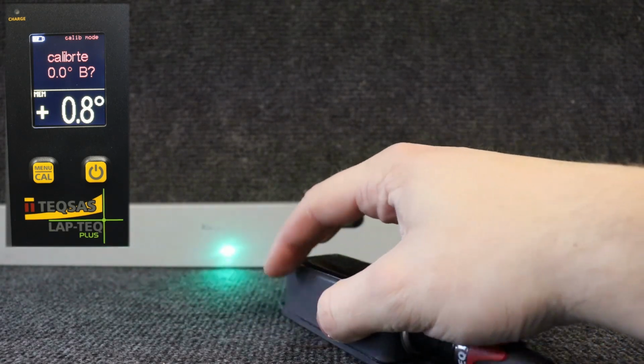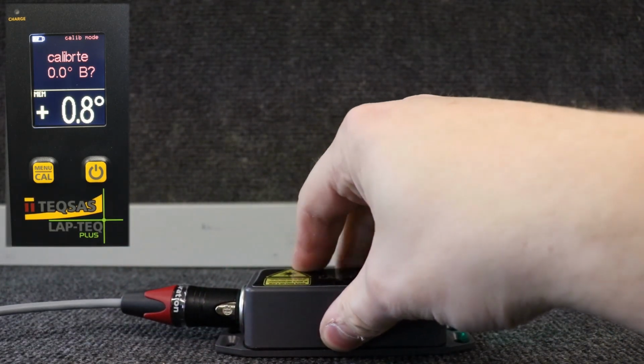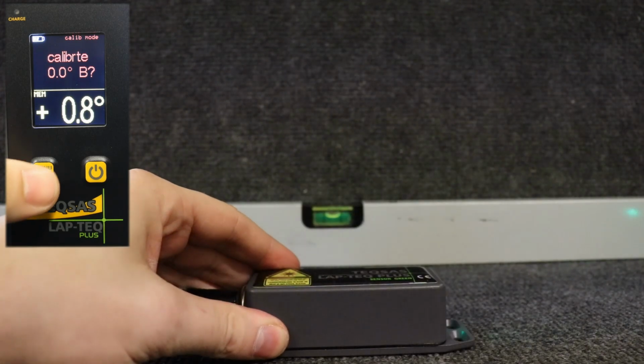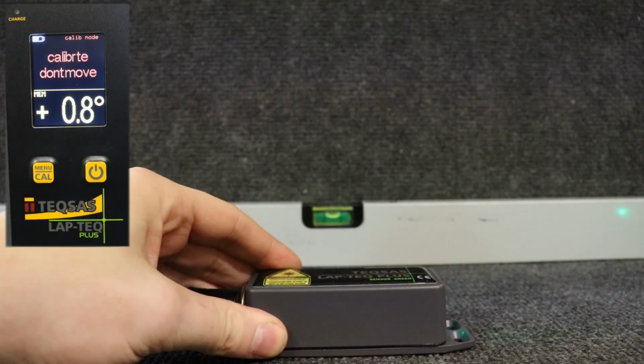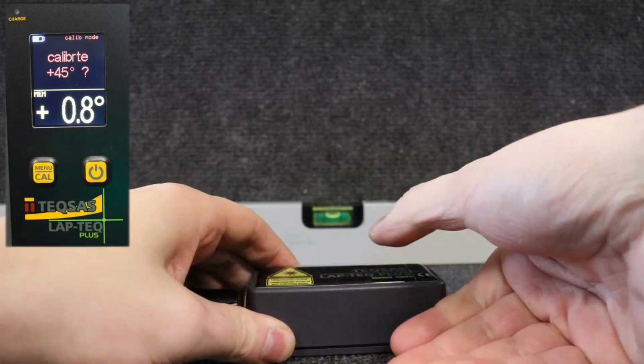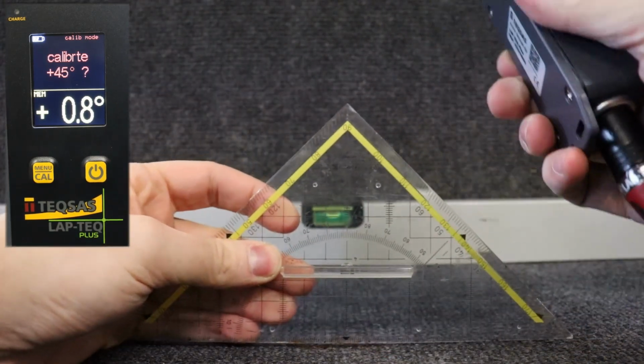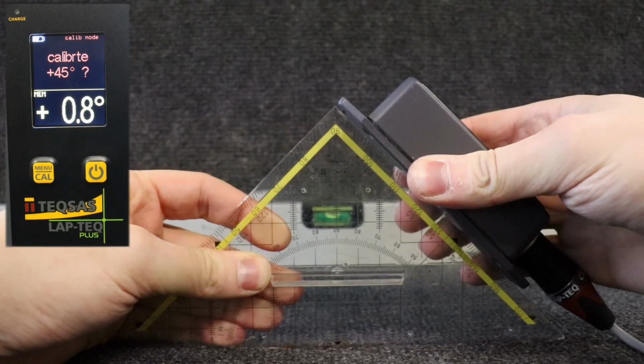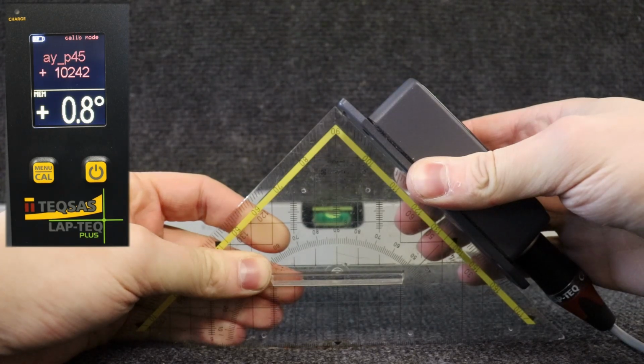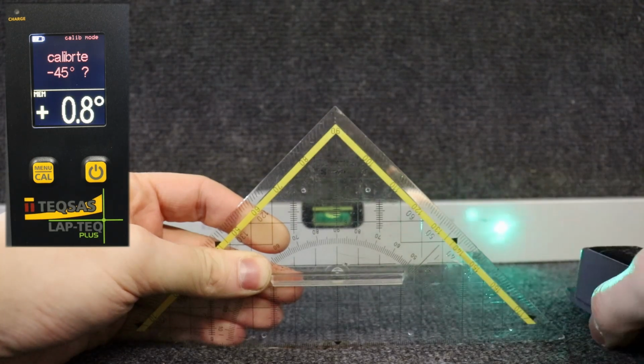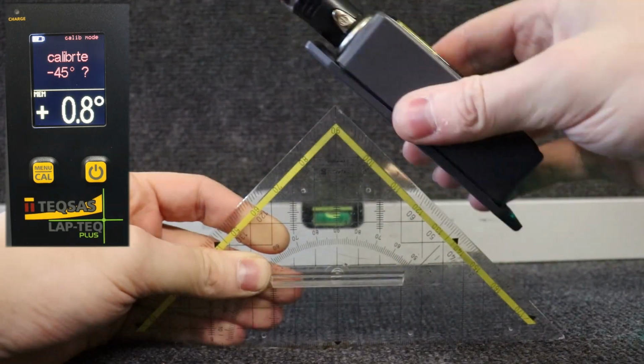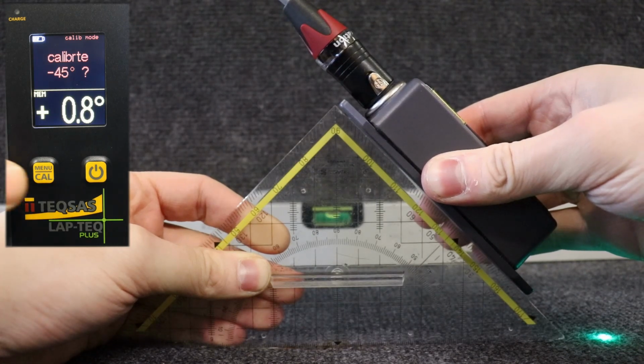For step 2, position the sensor horizontal at 0.0 degrees facing the opposite direction. Press Cal to start the measurement. For the third step, we must put the sensor at a precise plus 45 degrees angle. Press Cal to start the measurement. For step 4, position the sensor at a precise minus 45 degree angle. Again, press Cal to start the measurement.